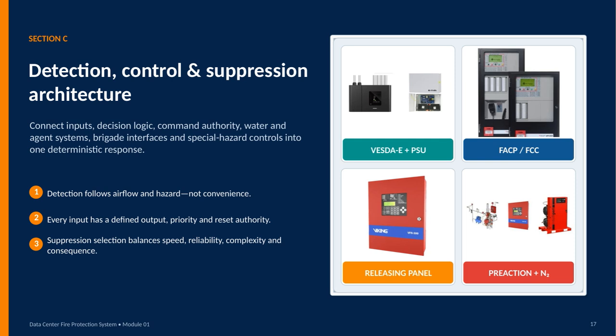The architecture shown here moves from VESDA detection and its power supply through the fire alarm control or fire command center, into the releasing panel, and finally to the preaction and nitrogen systems. Each connection should support a deliberate, traceable response from detection through suppression.